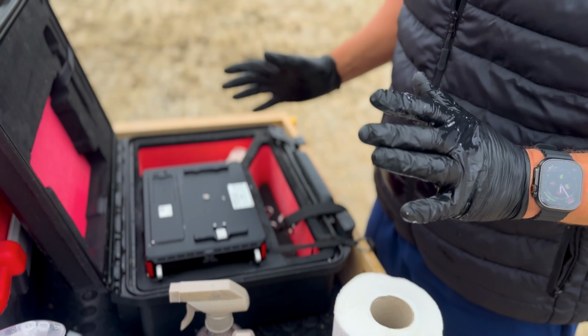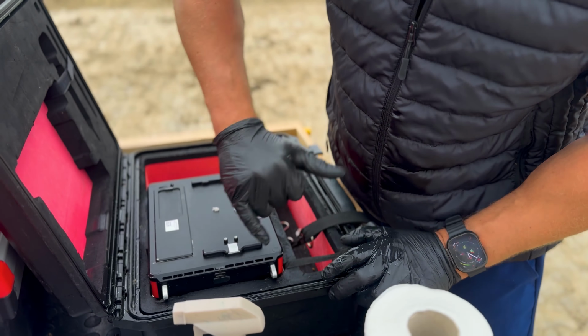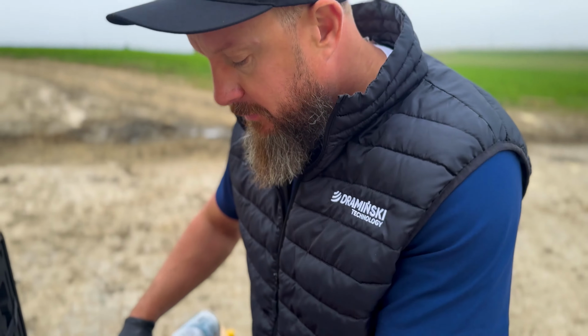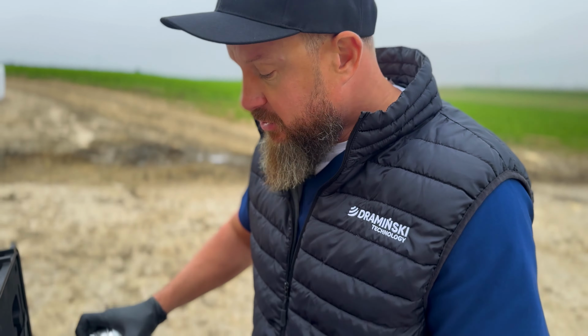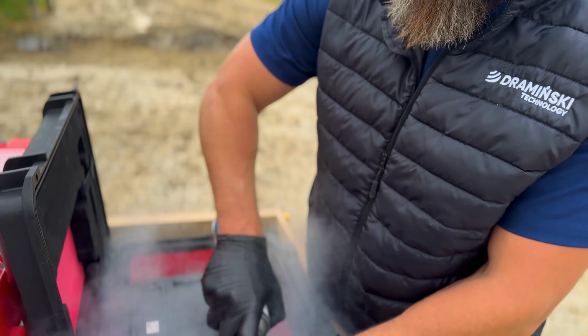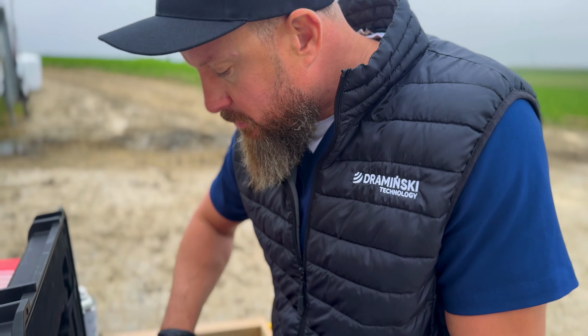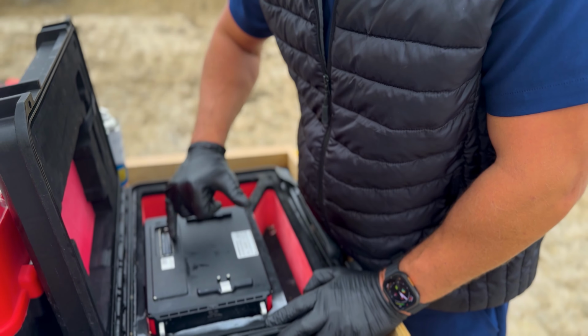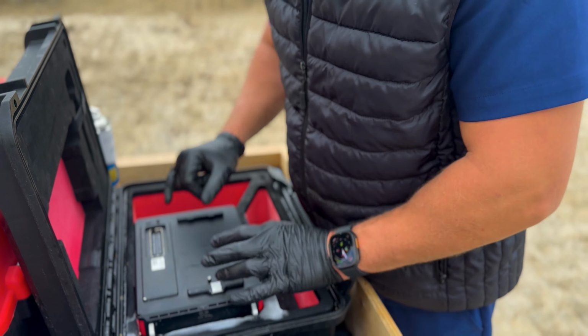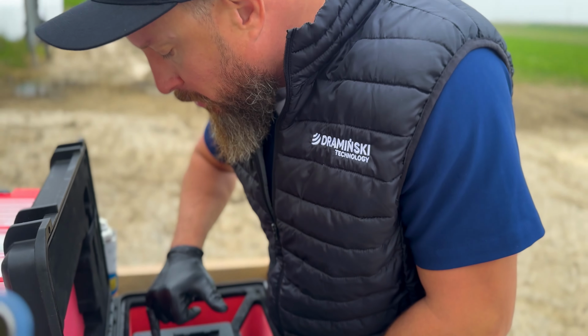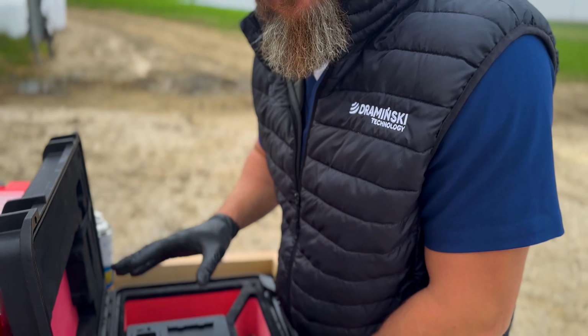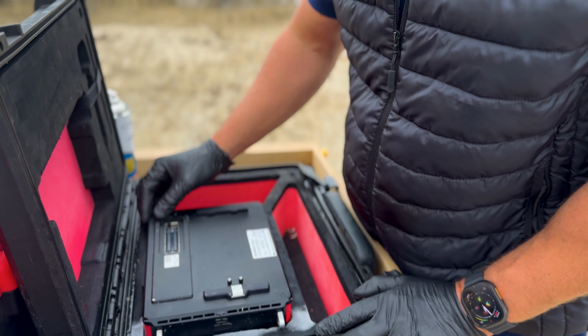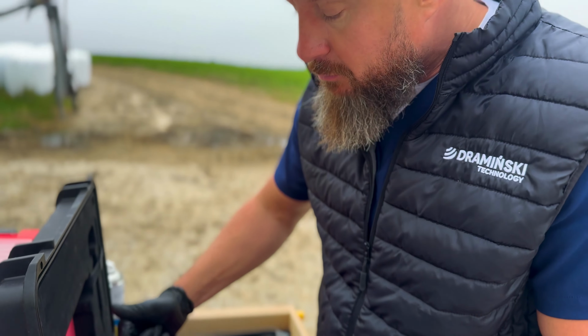If you work in the field, this part is often covered in dirt. You can blow out the vents with compressed air or an air spray. It's also good to blow out the probe socket from time to time so any micro debris gets removed. Such dirt can affect image quality.